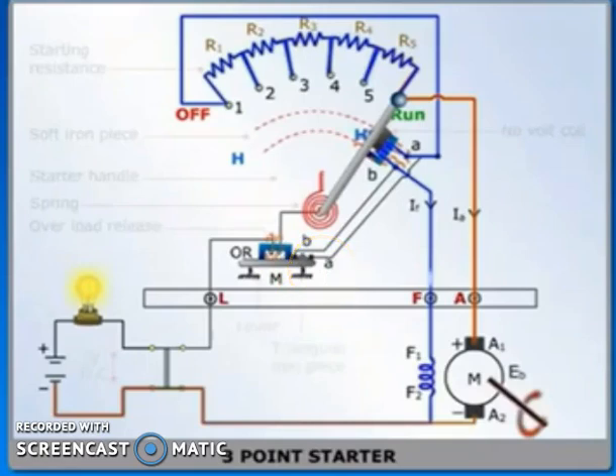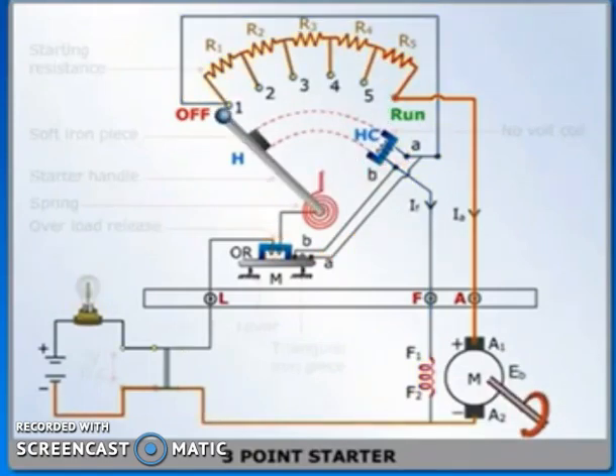As the soft iron arm is attracted, terminals A and B of the no-volt release HC get short-circuited. In this manner, HC gets demagnetized and the starter arm H is pulled back to the OFF position by the spiral spring. The motor is thus automatically disconnected from the supply in case of overload.